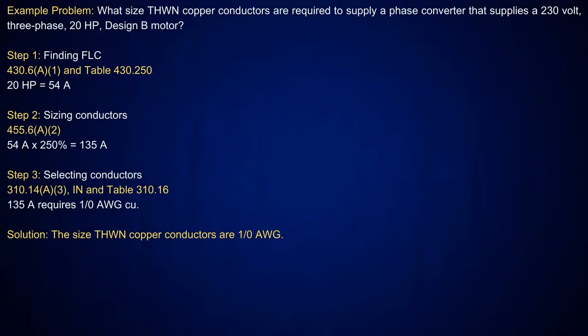And this in here, this deals with phase conversion. Now, what you're going to see is a little variance here from what we usually see. But this is where you're protecting the phase conversion on the conductors and everything. And they're going to tell you that the conductors have to be protected. In this case, you're still going to look at table 430.250 to get my amperage rating for the motor.